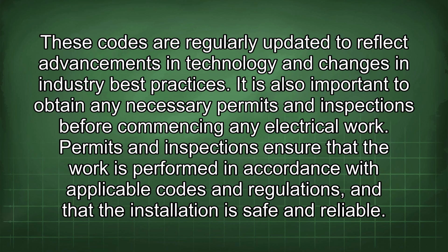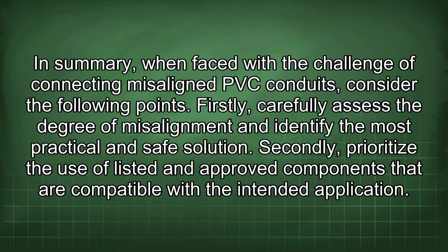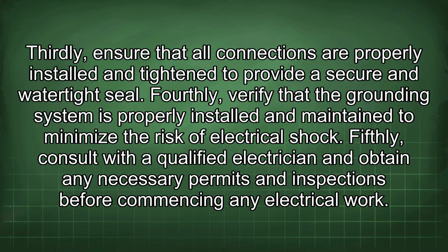In summary, when faced with the challenge of connecting misaligned PVC conduits, consider the following points. Firstly, carefully assess the degree of misalignment and identify the most practical and safe solution. Secondly, prioritize the use of listed and approved components that are compatible with the intended application. Thirdly, ensure that all connections are properly installed and tightened to provide a secure and watertight seal. Fourthly, verify that the grounding system is properly installed and maintained to minimize the risk of electrical shock. Fifthly, consult with a qualified electrician and obtain any necessary permits and inspections before commencing any electrical work.